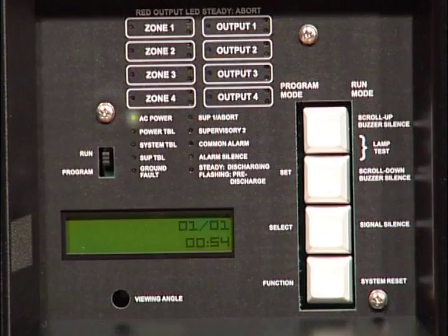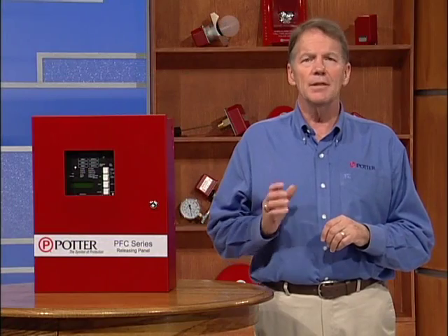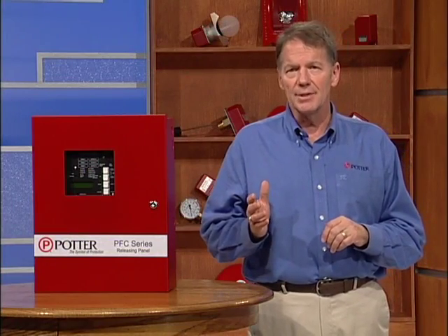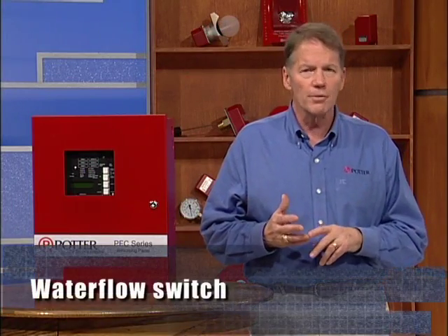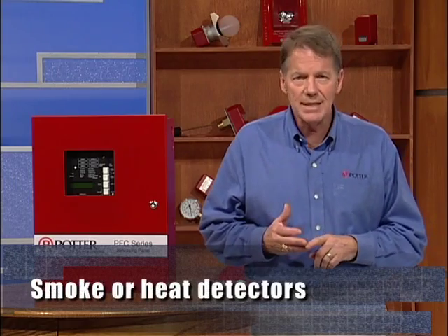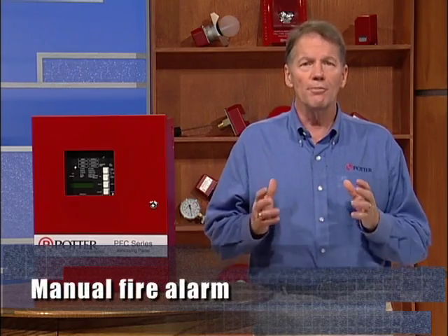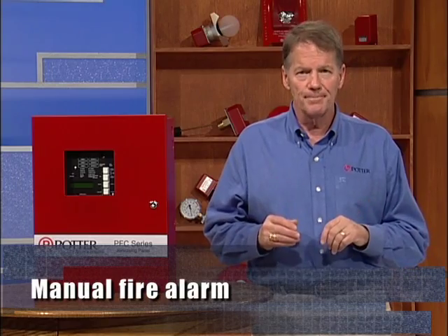The final releasing panel status is the alarm status, indicating that a fire emergency exists. Conditions that trigger an alarm status include signals from a water flow switch, a smoke or heat detector, or a manual fire alarm or pull station.